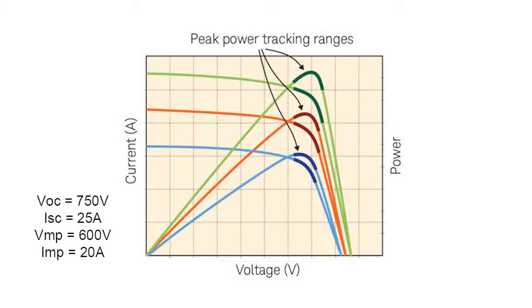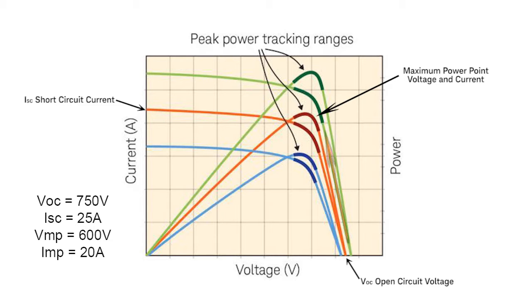I've pre-configured the PV simulator and what I've got it doing is tracking to a solar simulation curve which we program with the short circuit current and the open circuit voltage and current, and then the maximum power point voltage and current. So this is the output characteristic which corresponds to the following power curve. You'll notice what we expect the inverter to do is start at the open circuit voltage, increase power until it reaches the maximum, and that's where it's going to track to that maximum power. So once we power on the system we'll actually see that work.